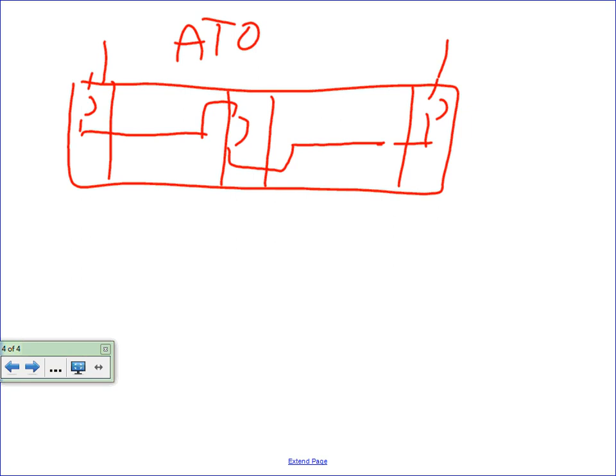We can do it with, like I said, what we call an auto throwover system. We actually mount PLCs and relays. We can do the same thing as transfer switches like that. We can do open transition, we can do closed transition. We can provide 3-pole breakers, or we could provide 4-pole breakers.